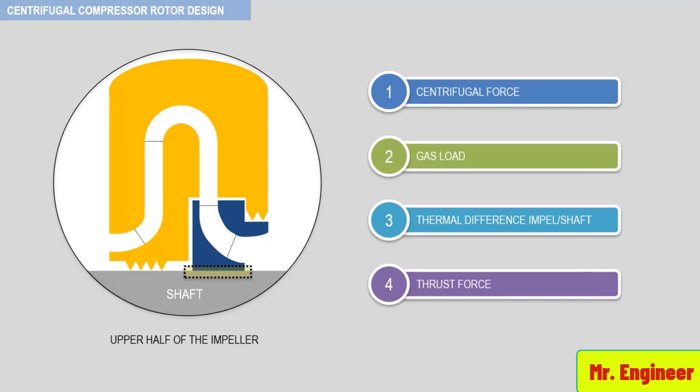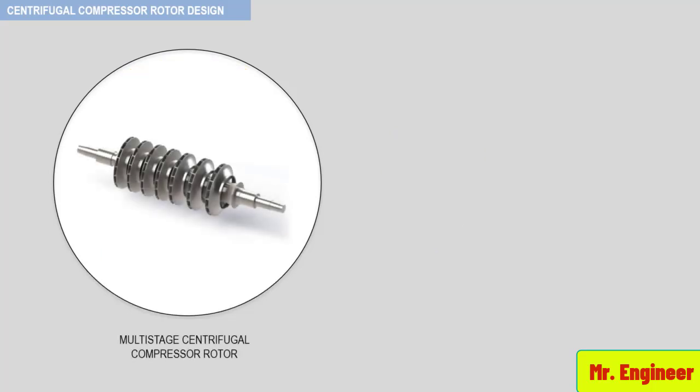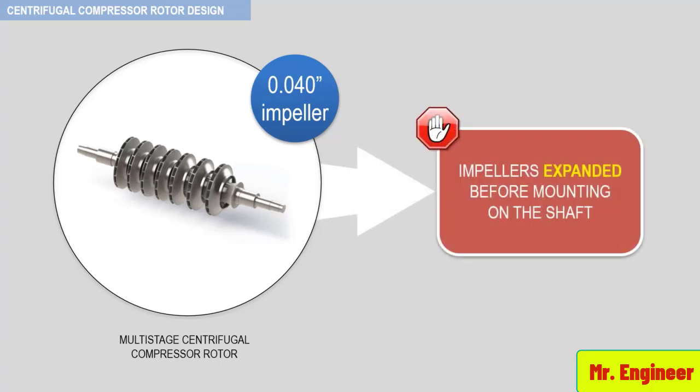Typically, impeller shrink fit values range from 0.002 to 0.003 inches shrink per inch of shaft diameter. Let's say that the rotor that you can see here has a shrink fit in excess of 0.04 inch for each impeller. In this case, the impeller would have to be expanded in excess of 0.04 inch before mounting on the shaft. Typical mounting stresses are 20,000 to 30,000 psi.